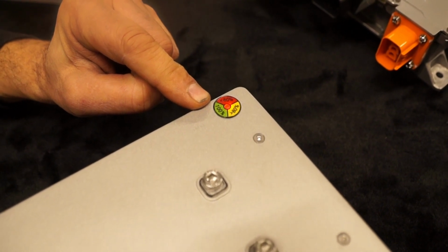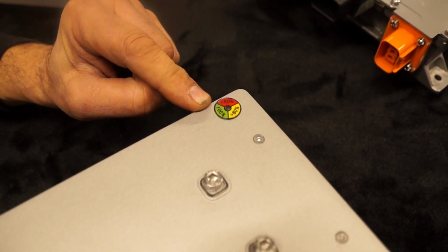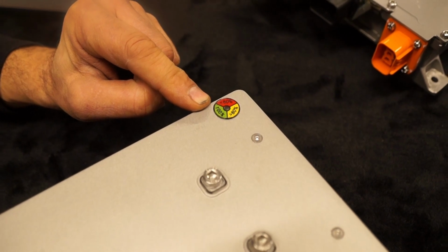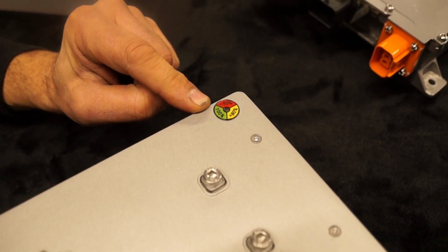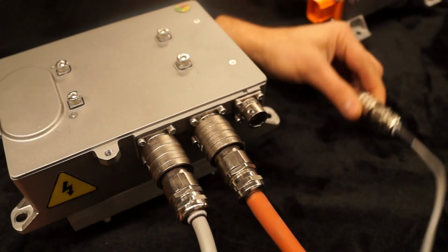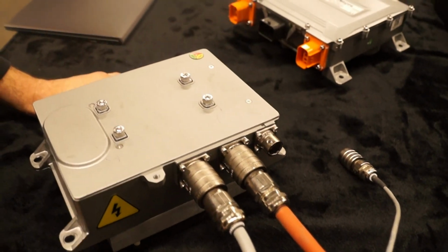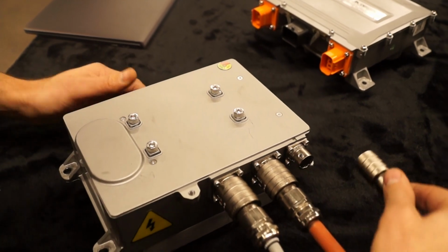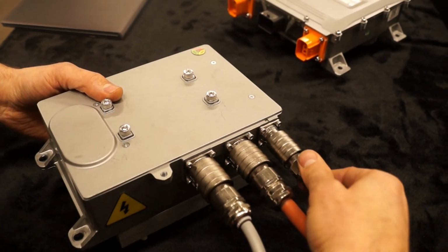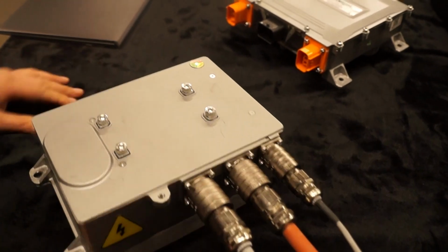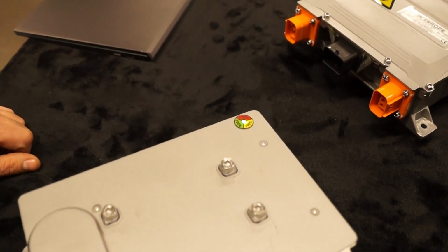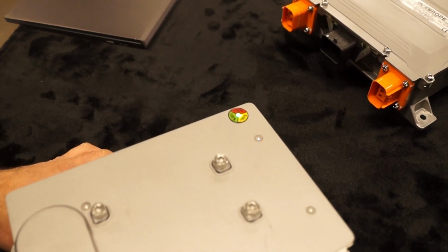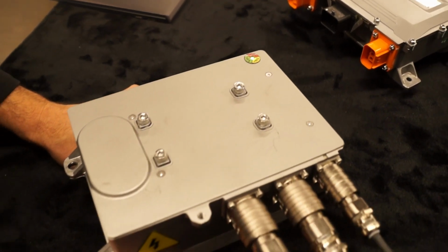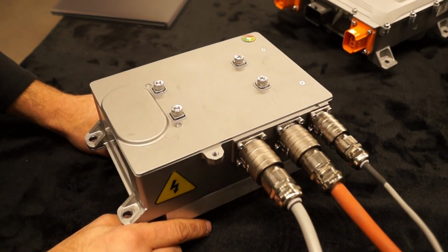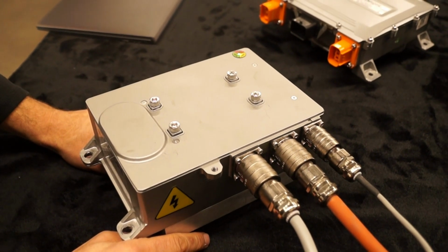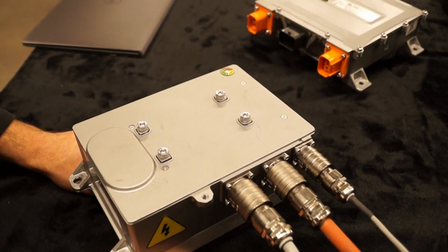So now we have the AC connected, and you will see the blinking LED. As you notice now, it's blinking red. The red blinking means there's no communication with the CAN bus. And that's correct, because we disconnected the CAN wire just to simulate the error it will give. So the next thing you will do is you can solve your communication issue. And you see that the charger is now giving a green LED. The green constant LED means it has communication, but it's not yet charging, because on charging it will start blinking only with the green LED.